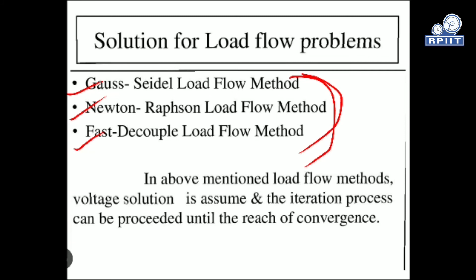So we will talk about the importance of why we go for load flow studies. The first one is that generation supplies demand plus losses. Basically from the generation we get the total active and reactive power, and the reactive power is mostly in terms of losses. By using this load flow study, we can limit our load demand and power losses. The second is that the bus voltage magnitude remains close to rated voltage, so there will be less chance of voltage fluctuation during operation if we do a proper load flow study. Then third is that generation operates within the specified real and reactive power limits. By using different calculation methods, that is Newton-Raphson, fast decoupled, and Gauss-Seidel methods, a number of iterations will take place, and we have to calculate the real and reactive power limits for optimum operation of generation.